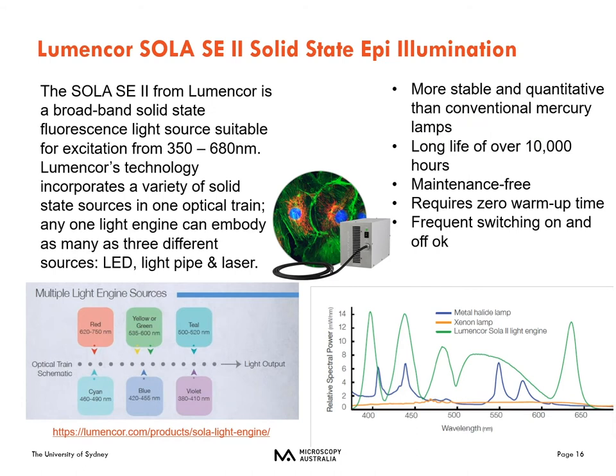What's becoming much more common is a solid-state epi illumination source. Many microscopes now use the Sola SE 2 from Lumencor, which mostly incorporates LED light sources to create a nice white light source. It is far more stable and quantitative than a conventional mercury lamp, has a very long life, requires zero warm-up and cool-down time, and no maintenance — you can just flip it on and off like a light switch.